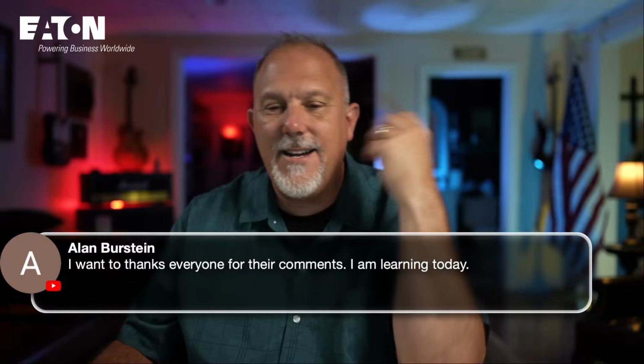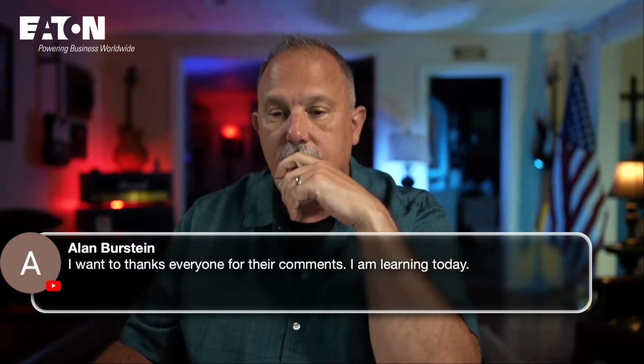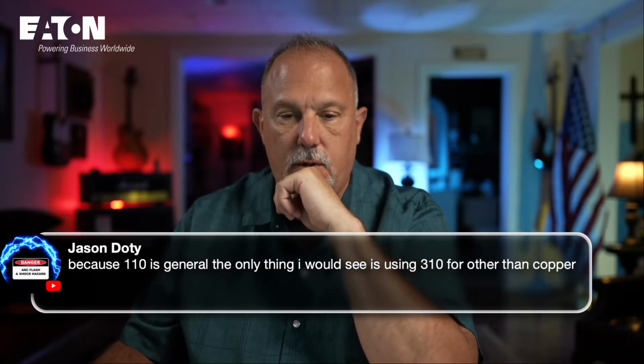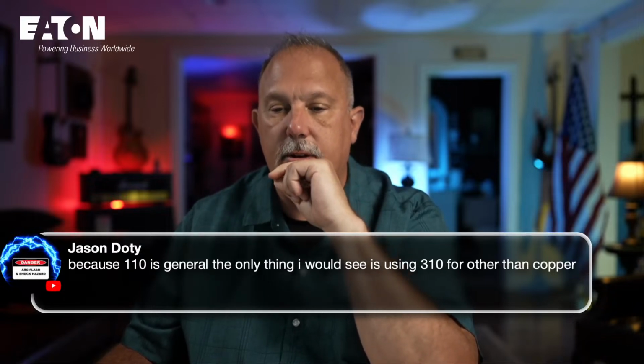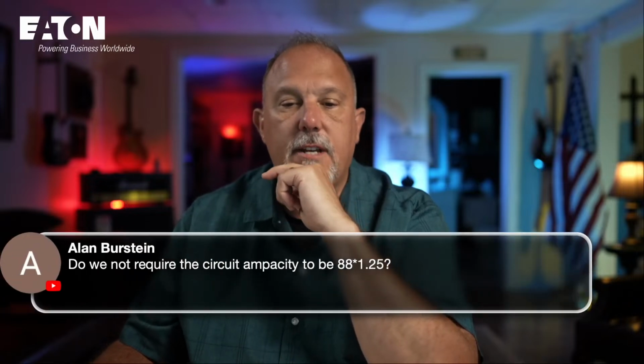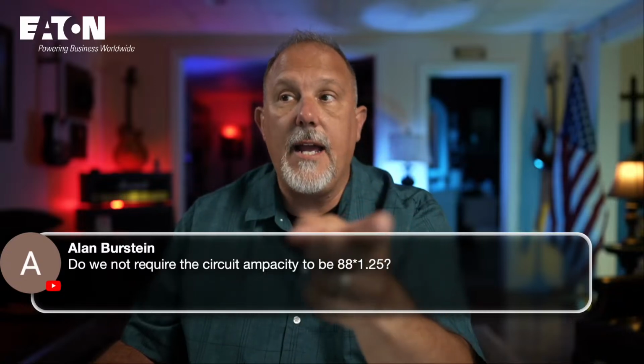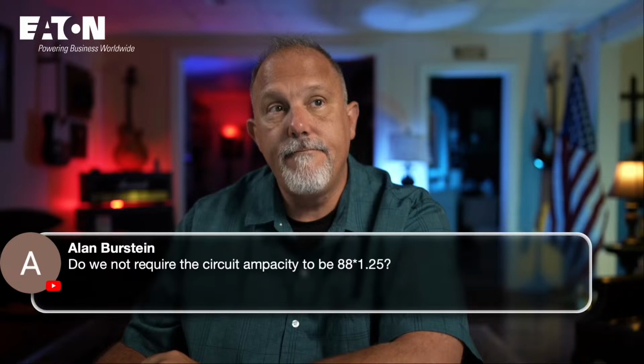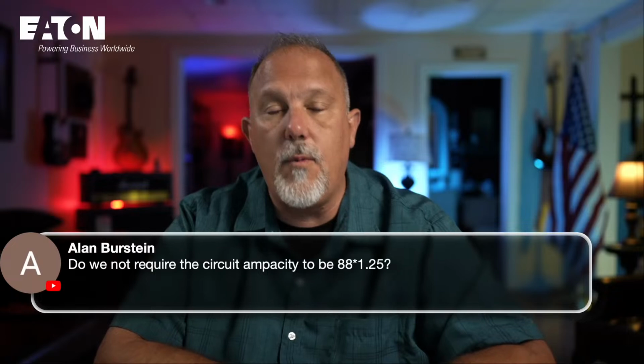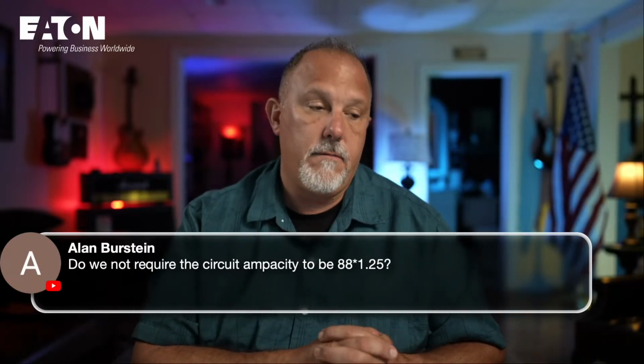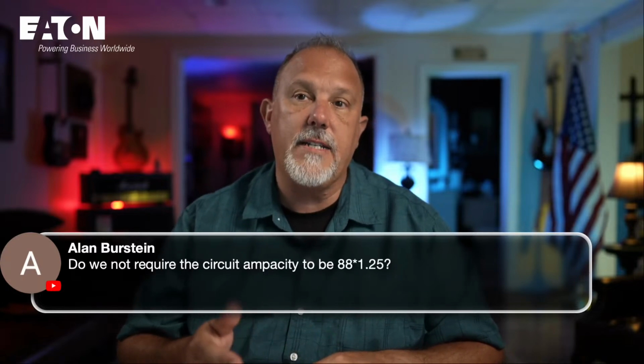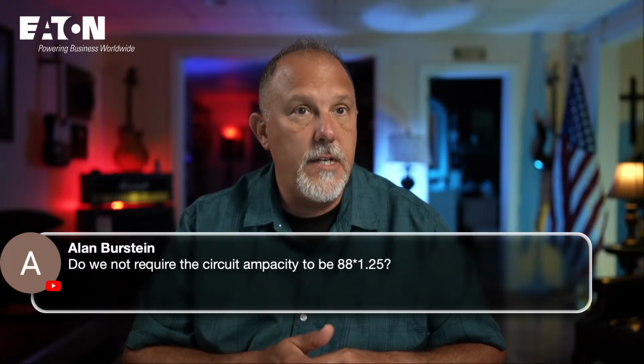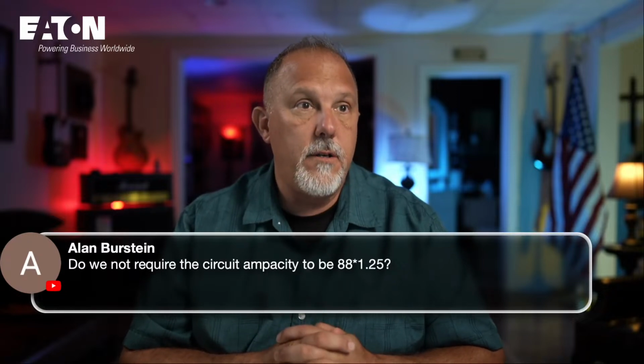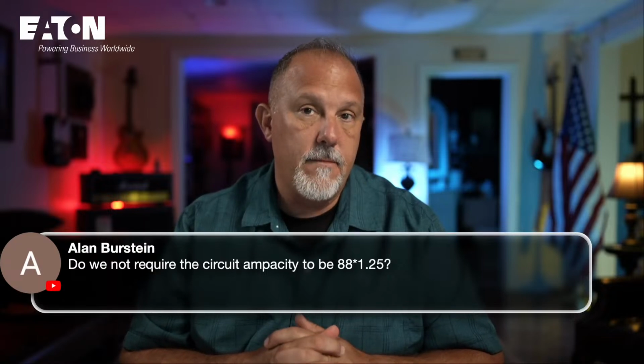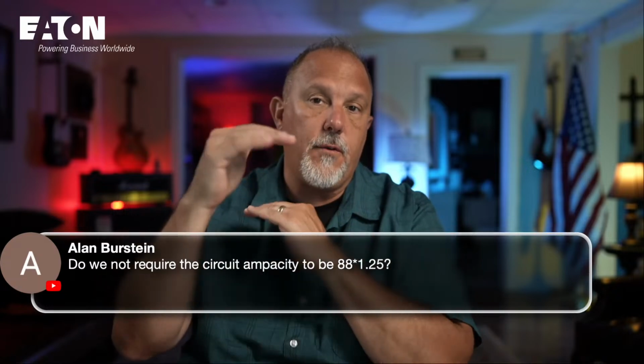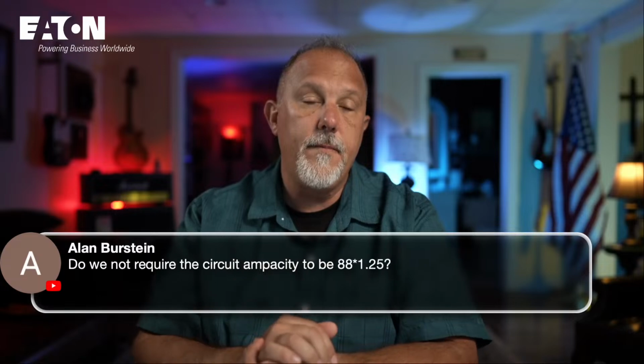I want to thank everyone for their comments. Excellent, Alan. Anybody who learns, I'm learning too. Excellent. Thank you. Jason, because 110 is general, the only thing I would see is using 310 for other than copper. Yeah, you're right. Yep. Do we not require the circuit ampacity to be 88 times 1.25? The circuit ampacity, no. No, Alan. The only reason we do the 1.25 is for the overcurrent protective device, right? Because the code says the overcurrent protective device has to be greater than 1.25. I don't have anything in the code that says the termination has to be greater than 125% of the continuous. I do the two numbers for the ampacity, the conductor, pick the larger of the two, and I move on.